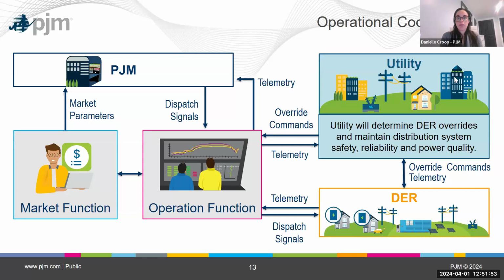The other important point is there are override commands. They go either directly from the utility to the DER, or from the utility to the aggregator's operations function and then to the DER. These override commands are in place if, say, PJM tells the resource to go up 2 megawatts, but that causes an overload or reliability concern on the distribution system. The utility can override PJM's commands and say, not 2 megawatts, you have to go down to 0, or maybe curtail to 1 megawatt. Some overriding function that the DER aggregator or individual DER resources needs to respect. The utility has ultimate override control because they operate the distribution system.